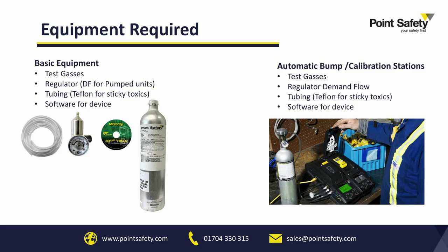One other thing that isn't included on that list is a calibration cap. Each detector will need a calibration cap that's suited to the detector, which will go over the front of the monitor where you apply your tubing. And this is individual to the meter. So each meter you're selling, you'll need those calibration caps in order to carry out a basic calibration. The same setup's required for bump testing. You don't necessarily require the software.